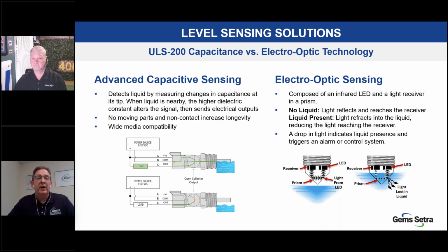On the left side, the ULS 200 utilizes capacitance to determine if it's wet or dry. The capacitance when it's dry and in air is different than when it's in an aqueous solution, so it determines that differential by sensing wet or dry. When it becomes wet, the internal signal changes, letting your equipment know you've got enough coolant in line, or that you don't have enough, or nothing flowing, by returning to its off-the-shelf state.